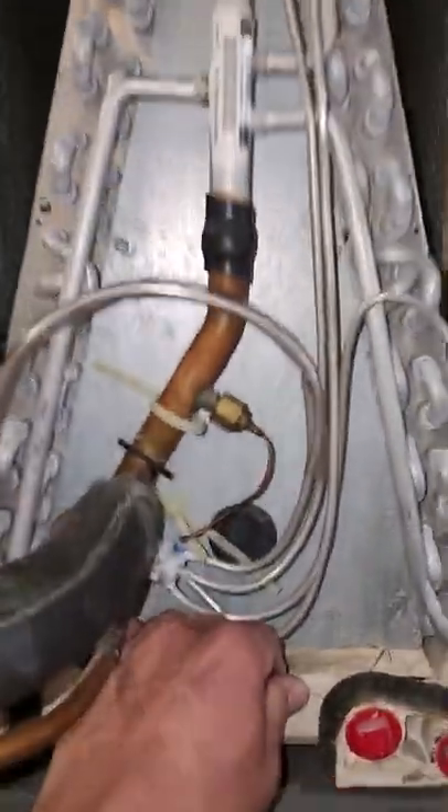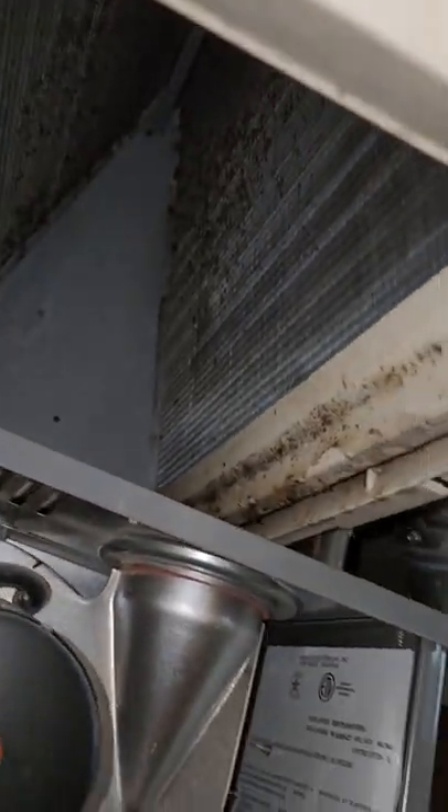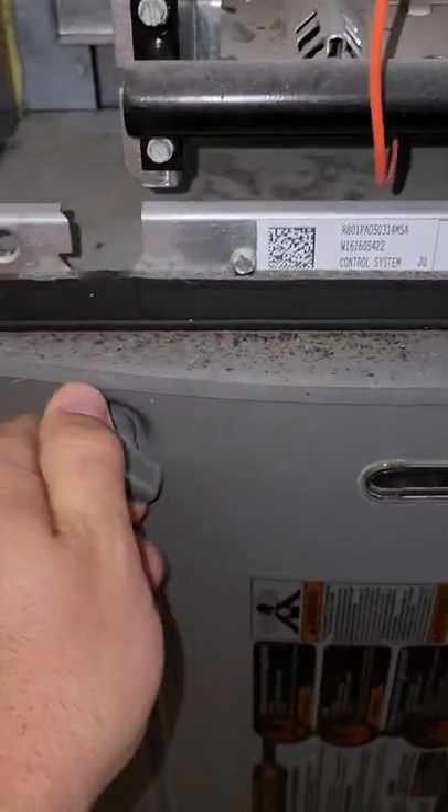What they typically miss — and if I can pull this out real quick — as you can see all the growth up here, which yeah I can clean that out, but I've had to do a lot of work on the gas lines and everything to get this out. There's no sense in cleaning the coil from the top if they don't come in and get all of this stuff out. And as you can see, those are roaches. Brand new carpet, all painted walls, everything — these are roach eggs, and that's why I'm wearing a mask. Come down here and there are more roaches, and this is all the stuff you're going to breathe in. If we take a quick peek inside here — piles of roaches.